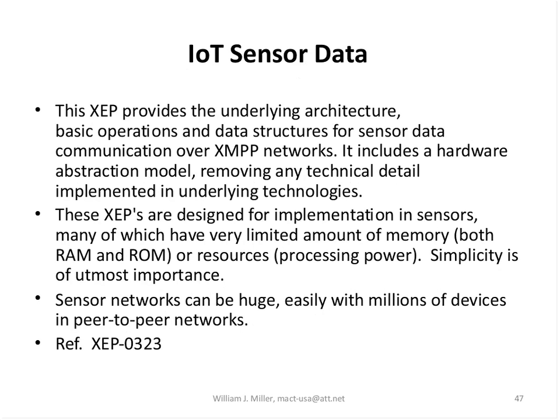Another XEP that's very important is called sensor data. That's one which you will use to read various devices in your network. And it basically abstracts all the information about that device. So when you would have provisioned that device, you would have already supplied a lot of that information, what its engineering units are and so on and so forth. So we're not having to remember any of that. Again, this is an attempt to keep things very simple and be able to pass just the actual data that we need. And as you can see here, simple.